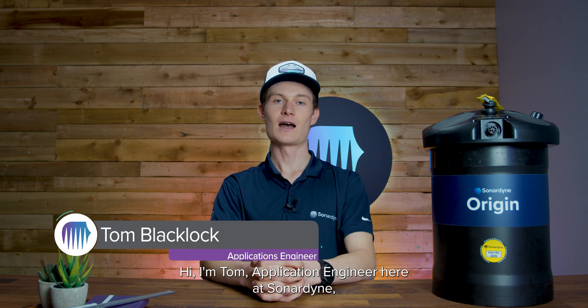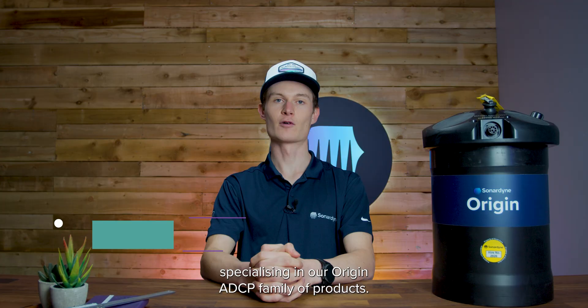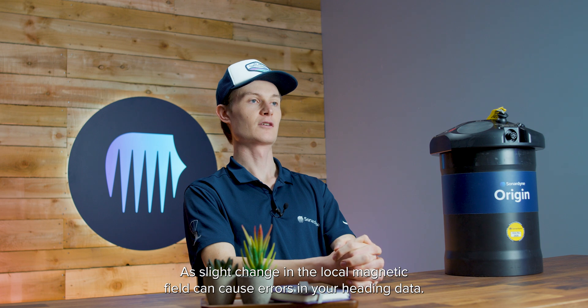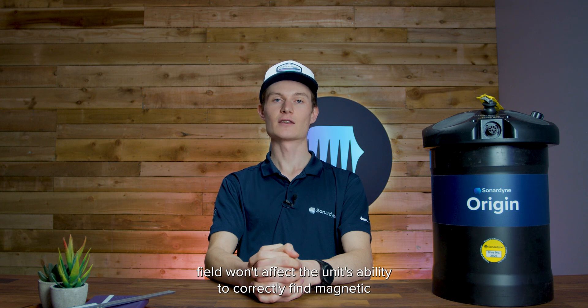Hi, I'm Tom, Application Engineer here at Sonardyne, specialising in our Origin ADCP family of products. Your Origin 600 requires calibrating before every deployment. A slight change in the local magnetic field can cause errors in your heading data. Calibrating the unit ensures that any change in the local magnetic field won't affect the unit's ability to correctly find magnetic north once deployed.